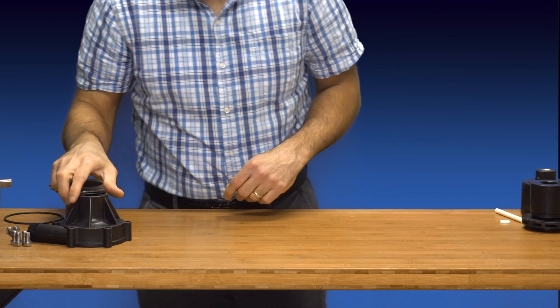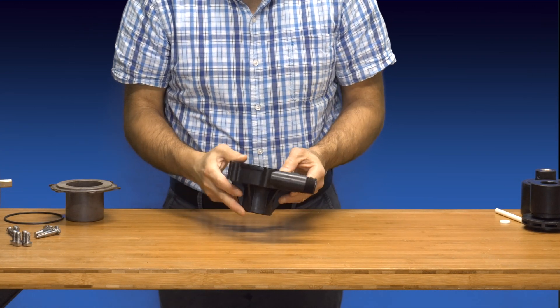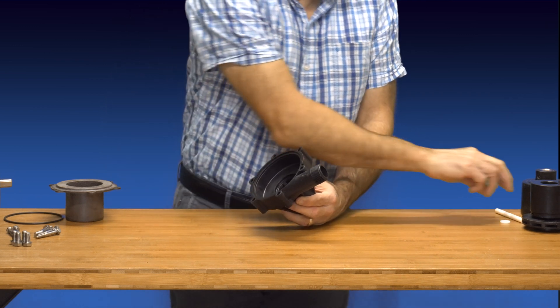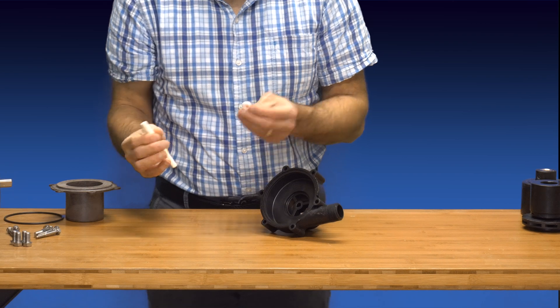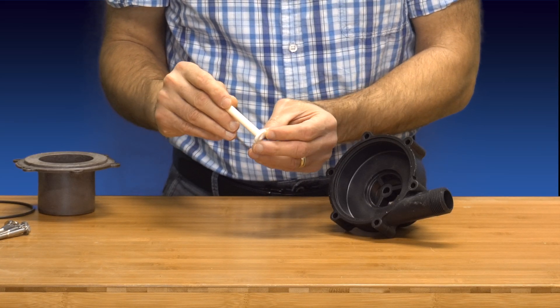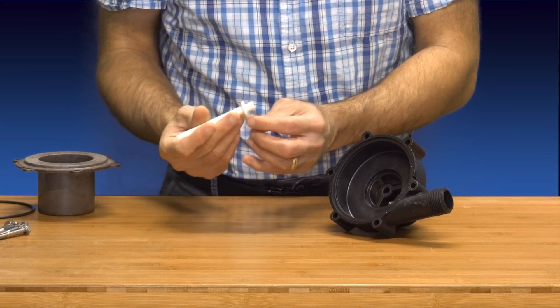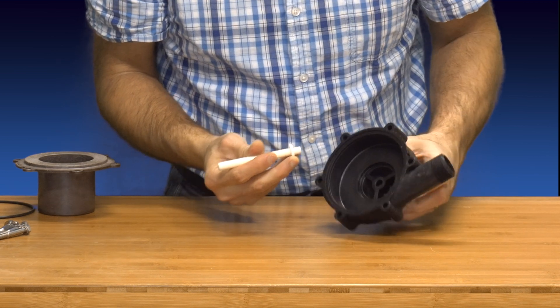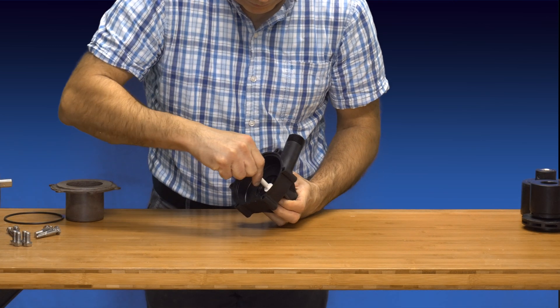We'll begin the assembly process by preparing the front housing. We'll take the pump shaft and thrust washer and slip the thrust washer over the end of the shaft, aligning their D-shapes. With these two parts loosely assembled to each other, we'll take the end of the pump shaft and insert it into the D-shaped hole in the front housing. Press it in firmly until it stops.